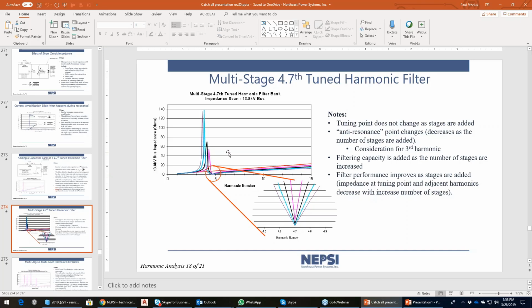So another reason to tune below the 5th and to provide some margin between the 5th and your tuning point is to allow for variation in capacitance and reactance, so that you do not have an inadvertent resonance at the 5th should this whole curve shift to the right.